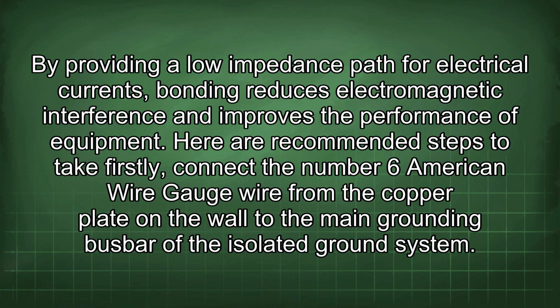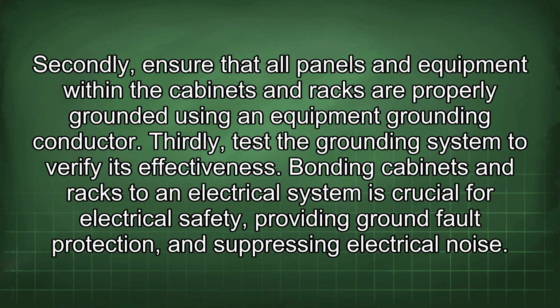Here are recommended steps to take. Firstly, connect the number 6 American wire gauge wire from the copper plate on the wall to the main grounding busbar of the isolated ground system. Secondly, ensure that all panels and equipment within the cabinets and racks are properly grounded using an equipment grounding conductor. Thirdly, test the grounding system to verify its effectiveness.